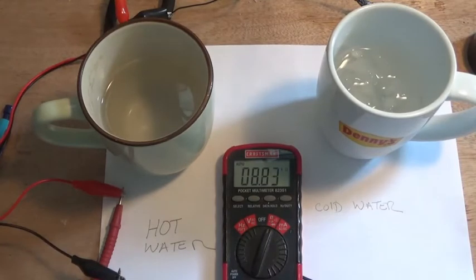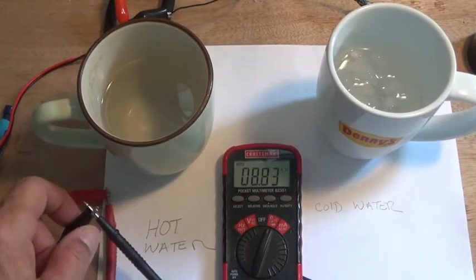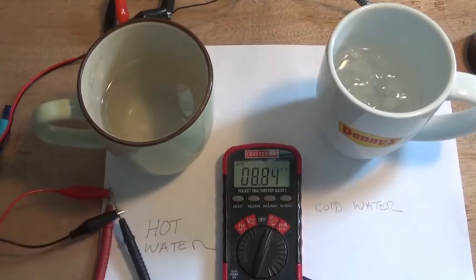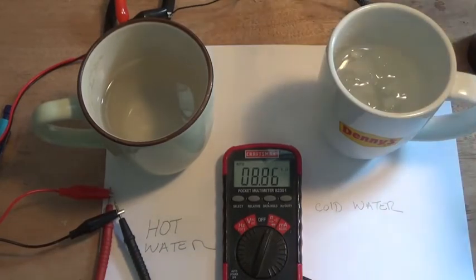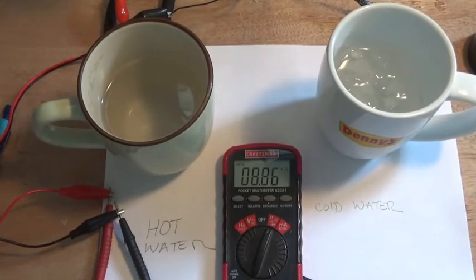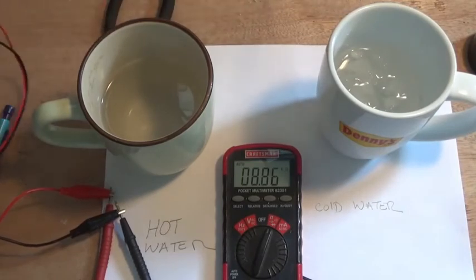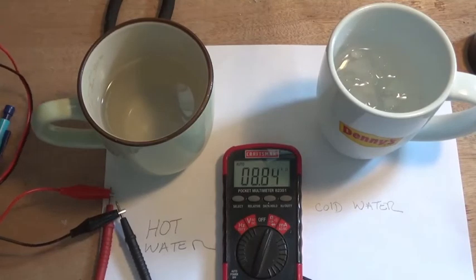Remember that the calibration shall be done with the length of cable that you plan to use. It might add a little bit and change your calibration a little, so be sure that you are ready to use the cable at the length that you're planning to use. Right now, let's see. This is room temperature, whatever it is, which I don't know. Might be about 85 degrees, I mean Fahrenheit, 85 degrees Fahrenheit. So it might be close to, I don't know, 27, 28 degrees centigrade.